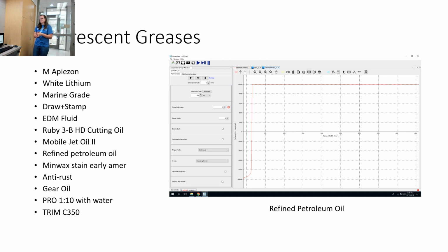Can you give me an idea what the maximum signal is up there? I think it was around 180 to 200,000 counts, on a baseline of like 300, so signal to noise is huge. And your integration time? Typically I kept it at 1,000, which is 1 second, which may be kind of high.